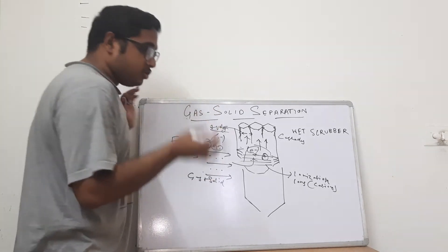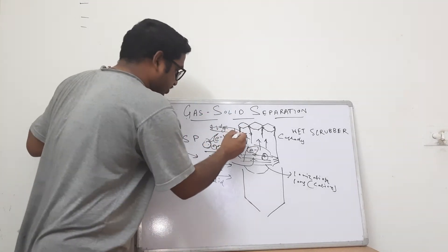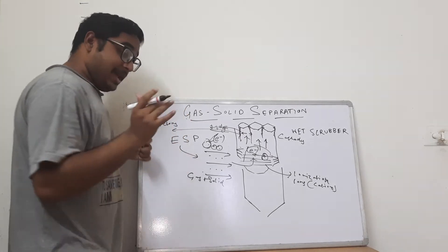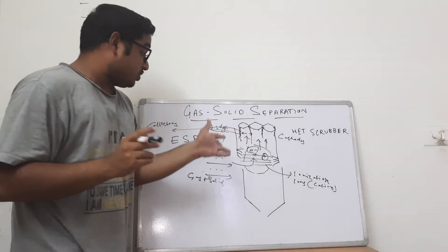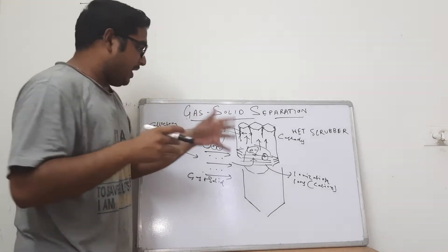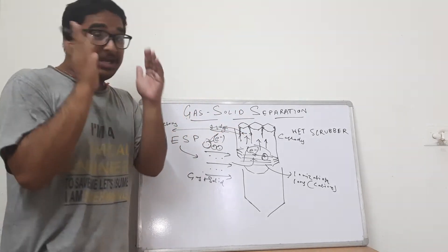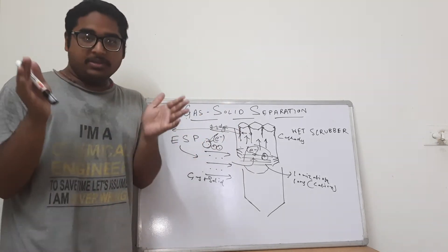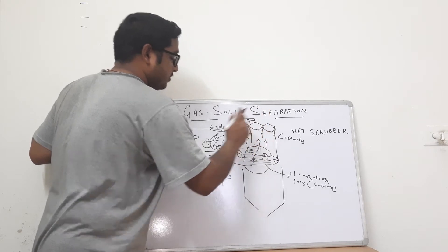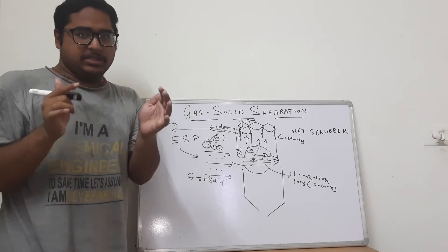The electrons deposit on the solid particles in the charging portion, and then in the collecting section — called the collectors — the solids with negatively charged electrons deposited on them get attracted towards the positively charged cathodes or electrodes and are thereby separated from the gas-solid system. The pure gas then exits through the honeycomb exit structure.